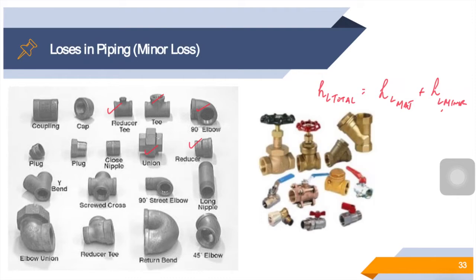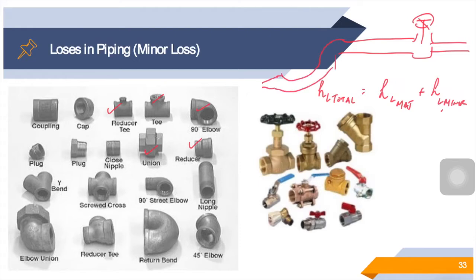In a typical system with long pipes, these losses are minor — if you have a very long piping network with very few valves, the minor losses are not very significant and major losses dominate. However, in some cases minor losses can be greater than major losses — for example, in a system with several turns, elbows, reducers, expanders, and tees, minor losses become the majority. For instance, a partially closed valve may cause the largest head loss in a system, as evidenced by the drop in flow rate.